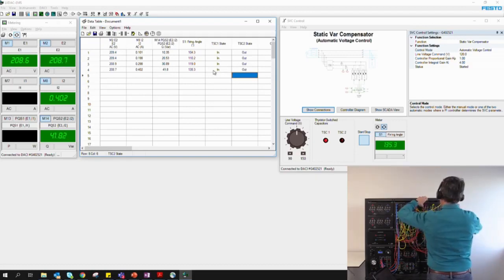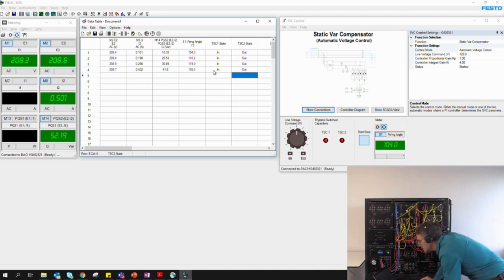From 300, we will go to 240. Recording, and now you see that TSC2 has been inserted into the circuit, which allows the firing angle to go back down, letting the inductors absorb more reactive power.